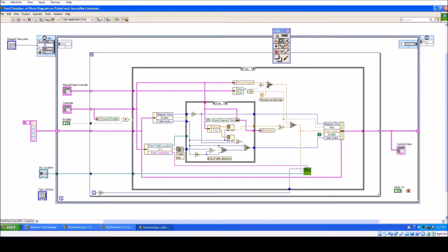But let's go back here now. So now what happens here is if stop is 1 or true, this will be false. And what we will do here is we will then take the false branch, meaning we will put the 0 into the manual speed. If stop is not true, meaning it's false, then we will pick the manual speed and pass it through. So the output here is either the value of manual speed or 0, depending on how these guys are set.